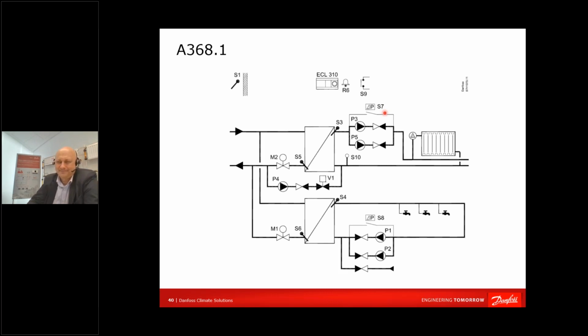All right. May I ask also a second question about the automatic filling line? Sensor S10. Basically, in this place we can use a pressure switch as well as a pressure sensor. In which case would you recommend one or the other? And a second parallel question: if you compare the two circuit diagrams and the three circuit, because this S10, as far as I remember, we are able to connect only for two circuit diagrams, 3.6 and something. So can we also use the automatic filling line for a three circuit substation, with one domestic hot water and two heatings?